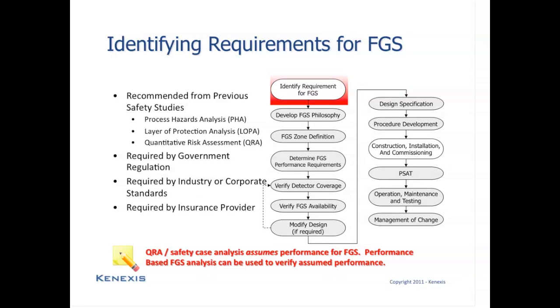These studies would include things like process hazards analysis, typically done using something like a hazards and operability study or a HAZOP, or checklists or what-if studies. There are many situations where the scenarios being considered under these process hazards analysis techniques will result in the study team being concerned that the existing risk profile is unacceptable and then making a recommendation for the implementation or at least the study of the use of fire and gas detection and suppression systems.